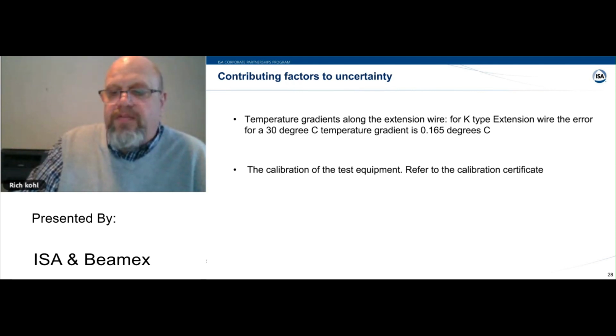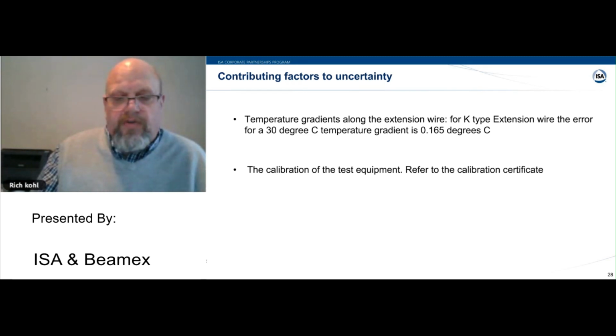It's an example of the effect of a factor that is specific to a function and the setup of your M&TE, your test equipment. Another one would be the temperature or the pressure gradient across tubing, which is generally negligible for under 10 feet of hosing. But if you have a real long distance, a whole lot of tubing in your setup, you can actually have a difference in pressures from the source end to the other end. So the bottom line here is you have to really know the function that you're testing.